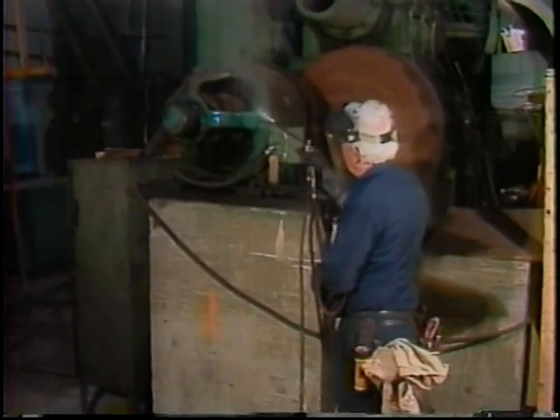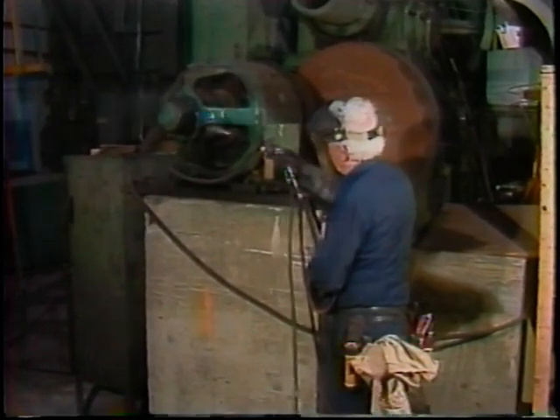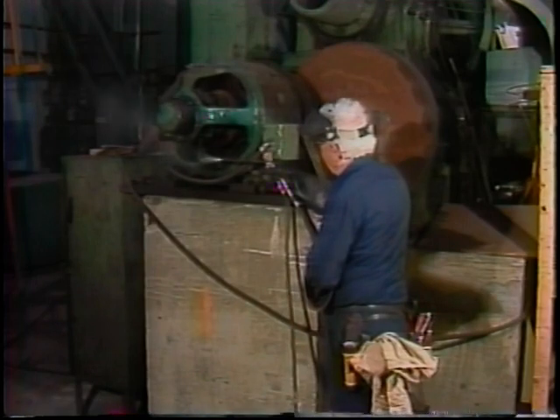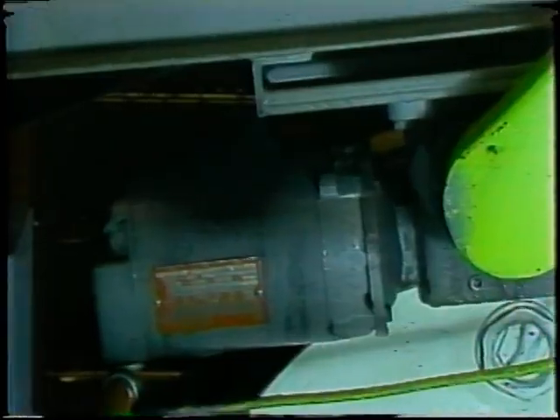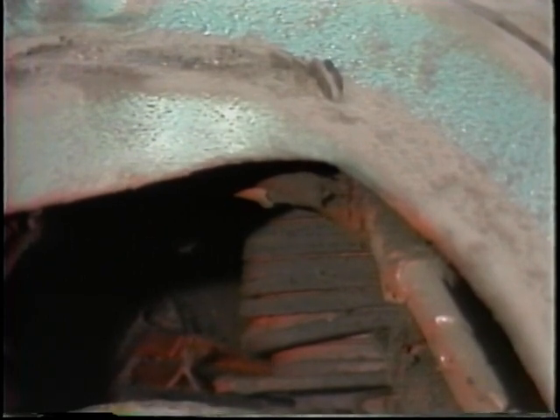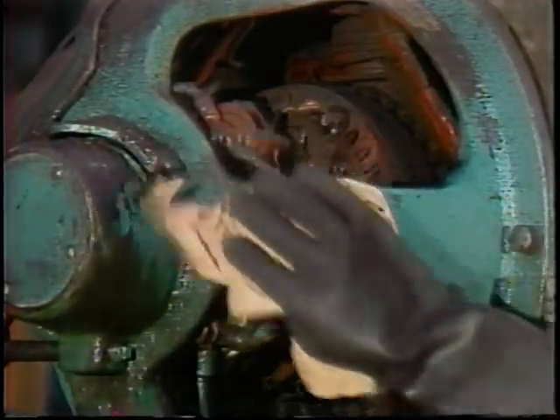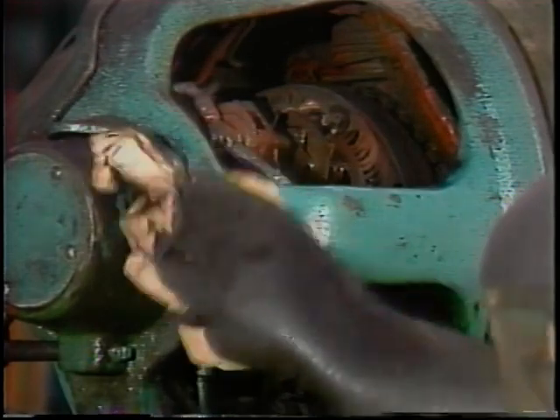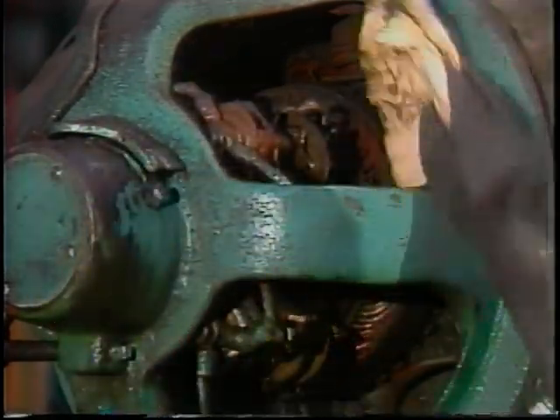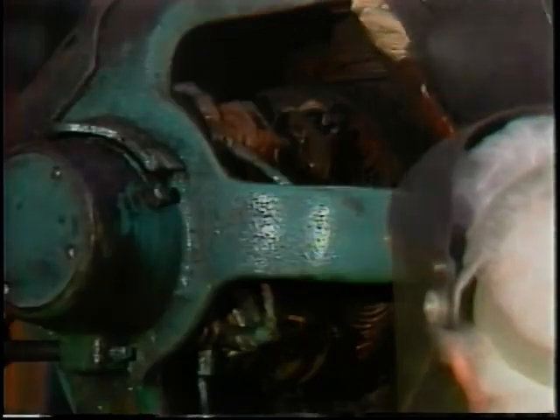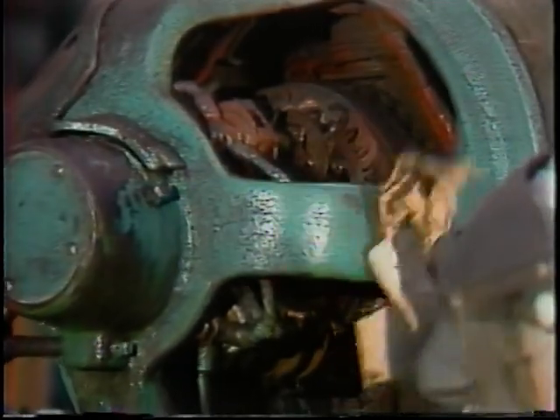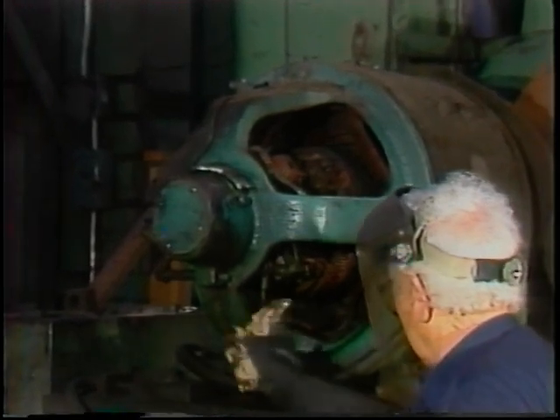Cleaning the motor helps it run cooler and last longer. Dirt interferes with free airflow through open motors and around enclosed motors and insulates parts so they cannot dissipate heat. Dirt can also damage insulation and allow arcing and current leaks. Wipe dirt off all motors and vacuum the dirt out of open motors if possible. Do not use an air hose, since the air blast can force dirt and grit down between the winding turns, where it will be more likely to cause insulation damage.